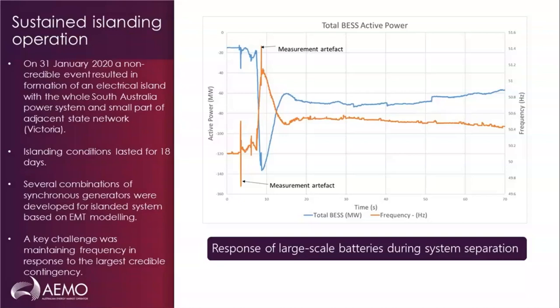Before moving on from this slide, the last point I wanted to emphasize here, and this is based on measured responses, is that as soon as, and in the process of, system separation, the batteries were connected, you can see that they provided a fairly fast response, which is faster than 1 second, which is orders of magnitude faster than what a synchronous generator could provide. This is an important aspect of the value proposition of batteries, which I would further emphasize in the next slide, which is indeed the last slide.